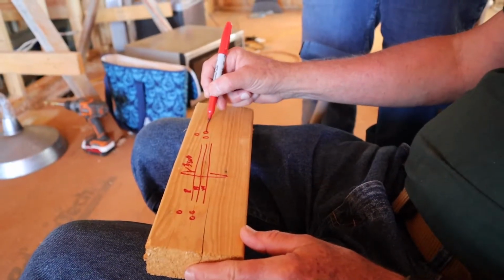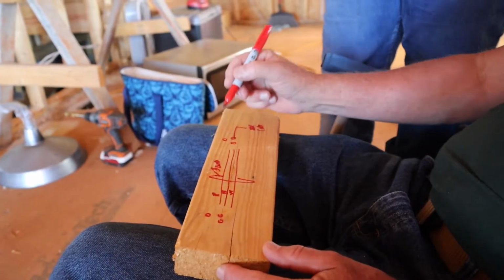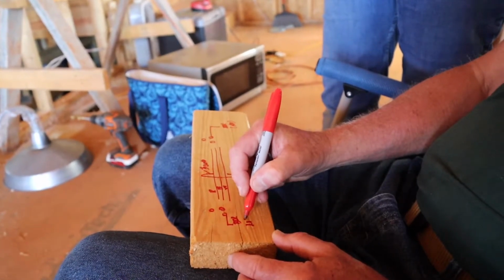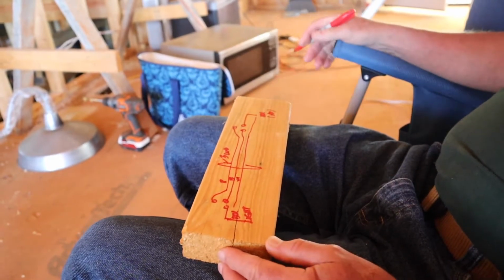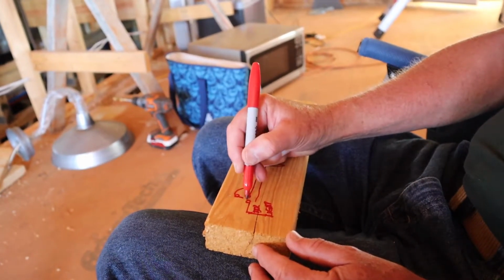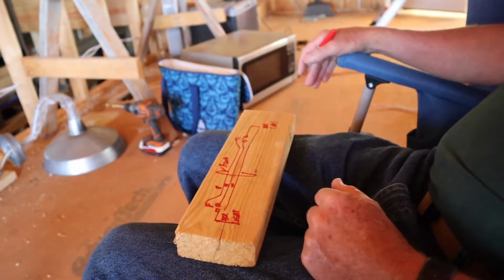Just from switch box to switch box. On one end, you will have the black, which is the hot wire, going to one leg of the 3-way switch. On the other end, you will have the black going to the light. You take these two and connect to the other two terminals on the three-way switch. So you have power coming into one side, a switch that will switch from one side to the other, and over here you have a switch that switches from one side to the other. At any point in time, this will switch hot, and depending on where this one is, it will switch it to the load. That's all there is to it.